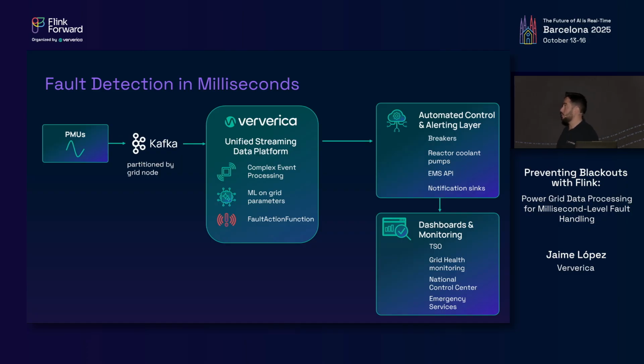That proposal hinges on using high-resolution PMU data on the extreme left, fed into an event bus at millisecond latency from the PMUs to a Kafka, for example. You can partition it by grid nodes so that you have different partitions telling you how things are going in each area. And you're going to be able to guarantee, when it comes into our data platform, exactly once semantics. You're going to be able to ensure that every event is in order, it's delivered exactly once, and you can perform the analysis that you need.